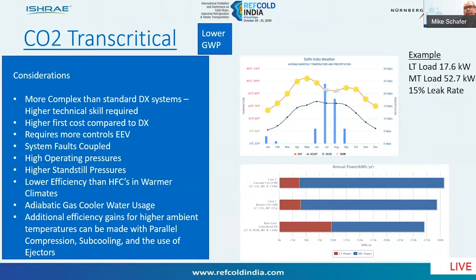And then looking at the annual power consumption for both the low temp and medium temp, you can compare the three different types of systems. In this example, looking at 404A on the low temp, 134A on the medium temp for the centralized DX system, and that would have the lowest power. The booster system comes in a close second, and the cascade CO2 system would have the most annual power.